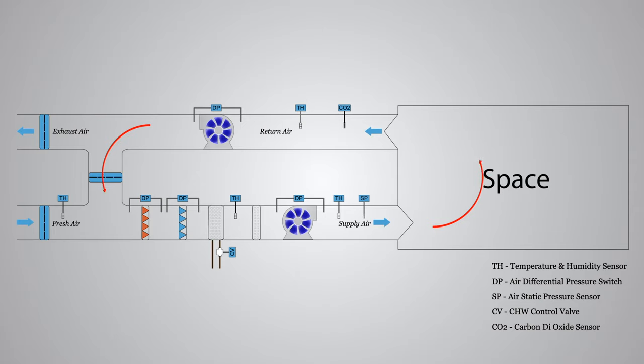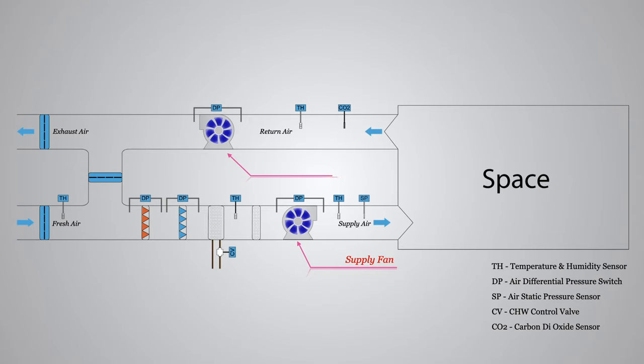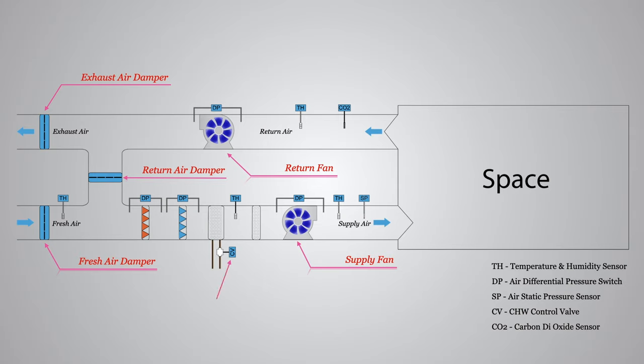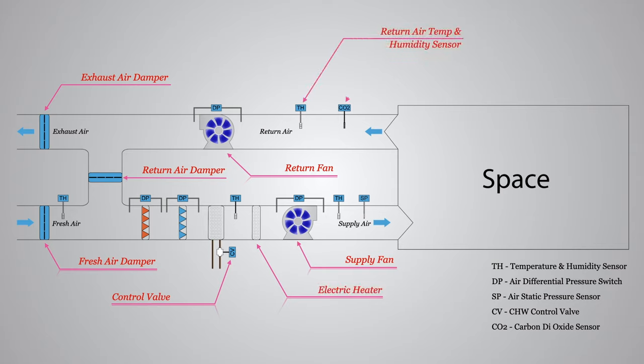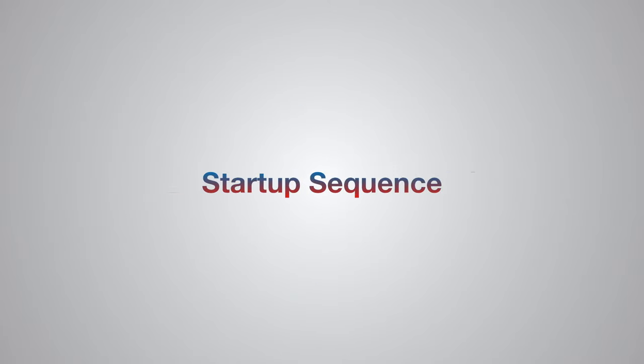This AHU is a recirculating unit with constant or single speed supply and return fans, with fresh air, return air, and exhaust air systems. The following sensors and devices are required as a minimum, which are monitored and controlled in the BMS: a fresh air damper with modulating actuator, an exhaust air damper with modulating actuator, a return air damper with modulating actuator, an electric heater, a return air temperature and humidity sensor, and a return air CO2 sensor. The remaining sensors are in place to monitor the system performance. Let's see how the startup sequence works for this AHU.